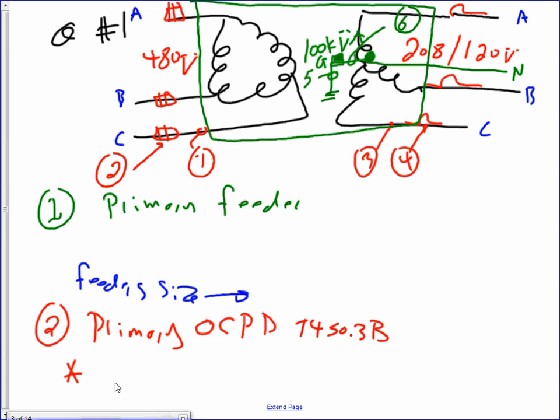Before I move on, any comments, any questions, what we're trying to achieve? We do have a transformer. On the primary side is 480. On the secondary side is 208/120. It's a delta-Y. We need to size the feeder and the fuse on the primary, the feeder and the fuse on the secondary, the main bonding jumper, and the grounding electrode conductor. Any comments, any questions? Does it make sense? Yes, no?